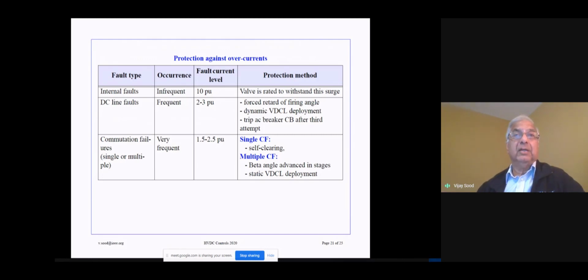The protection methodology that's going to be used is what we call the forced retard of the firing angle. We change the firing angle from typically 15 degrees alpha to maybe 145 degrees very quickly. We can change the firing angle, so we can go into inverter operation at the rectifier. And this way we can reduce the DC fault current.